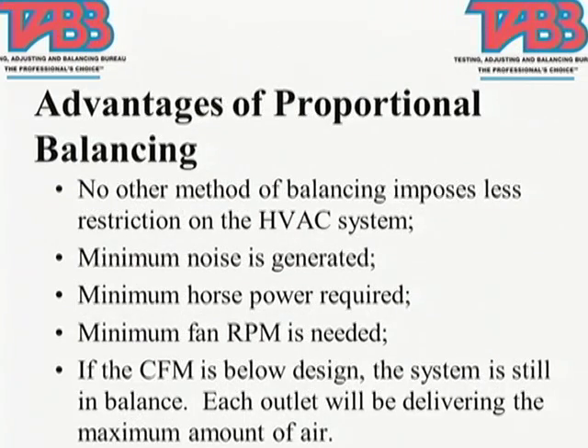One of the things that I see happening more and more today that never used to happen, it was always just in the books, and I do have to say it's happening because people want to be more efficient, is we used to never trim the impellers that often on pumps. We could calculate it. The balance report would come back and say you have an 8-inch impeller. If you trim it back to 7 5/8 inches, it'll run, it'll deliver all the water you need, or the hydronic or the glycol. And this building will save X, it'll pay for itself basically in about 6 months' time. But no one took the time. What they would do is say, well, let's put a valve on the discharge of the pump, and we'll just have it work against that for the next 80 years.